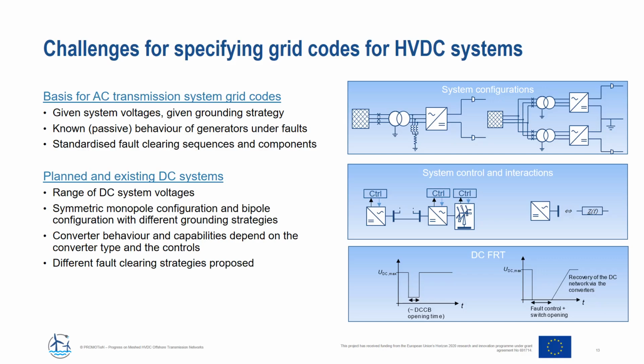Moreover, there are different fault clearing strategies proposed for the DC systems, leading to different possible DC fault ride-through profiles. So as shown in the bottom picture here, for a strategy based on DC circuit breakers, the left profile might be applicable with a certain DC circuit breaker opening time, but when applying, for example, fault blocking converters with a fault current control capability, the profile might rather look like on the right side. So it's very difficult to specify a generic DC fault ride-through profile which would be applicable for any grid code.